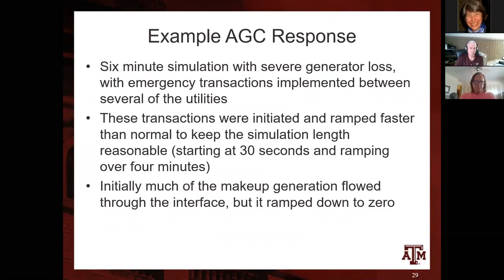Then I set it up to model the AGC response. In this particular scenario, which was a generator loss in the West, I set it up so that the makeup power is done by generators in the West. So they gradually ramp up over the course of several minutes, and conversely, the interface flow goes down.